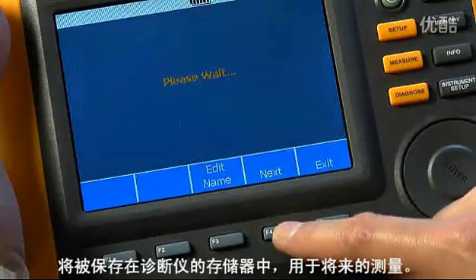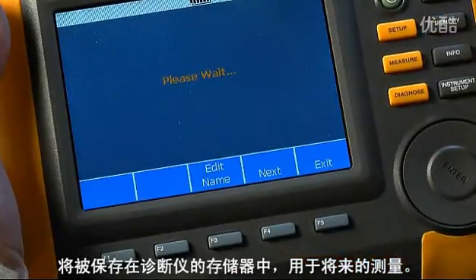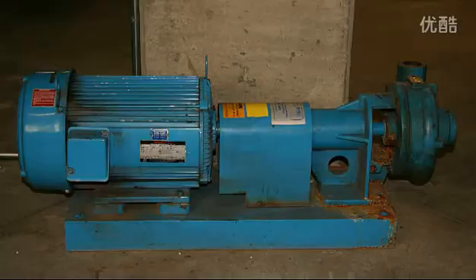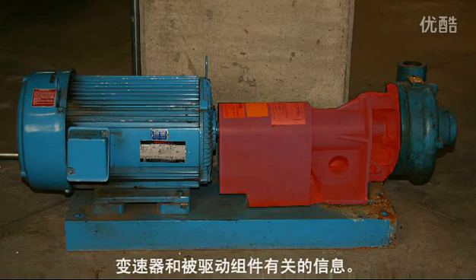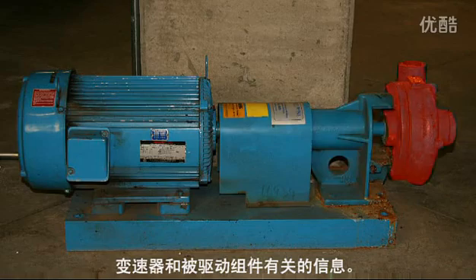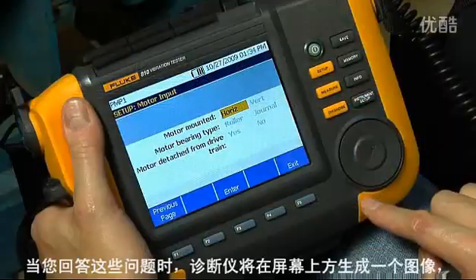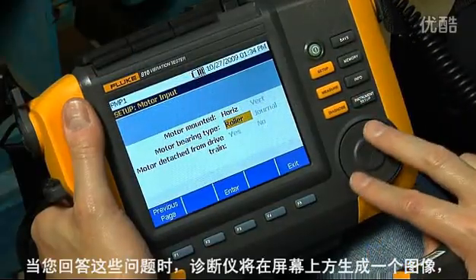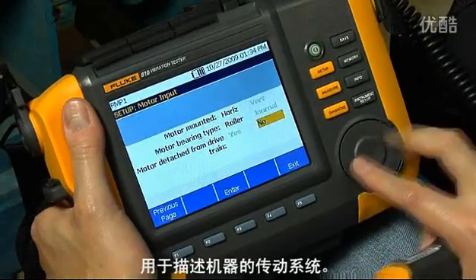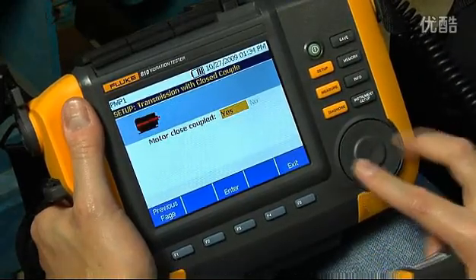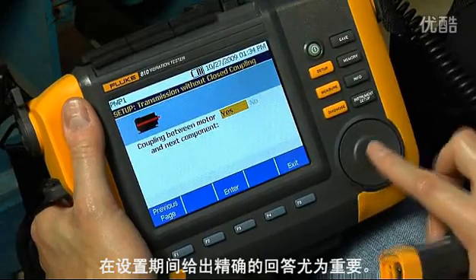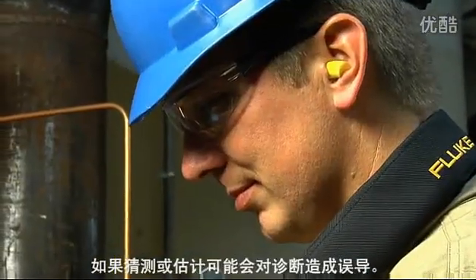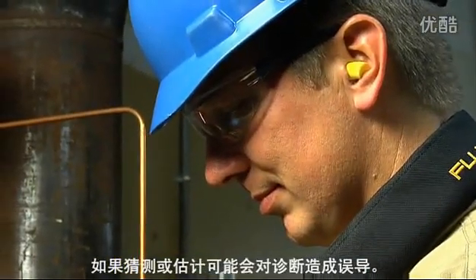Once completed, the machine setup will be saved in the tester's memory for future measurements. In the machine setup, the tester will ask you to enter information about the motor, the transmission, and the driven component. As you answer these questions, the tester will build an image on screen depicting the machine drivetrain. It's important to give accurate answers during setup — guesses or estimates may result in a misleading diagnosis.